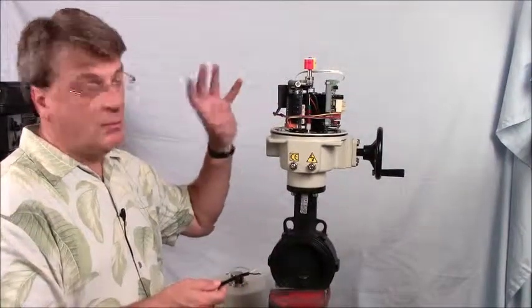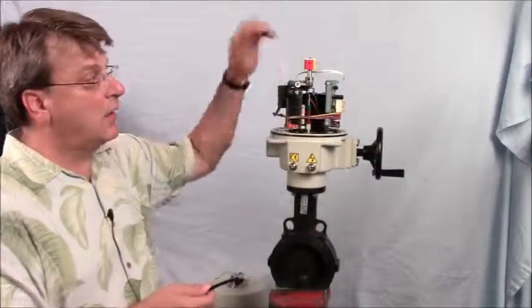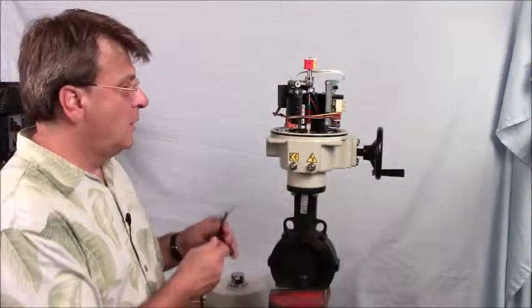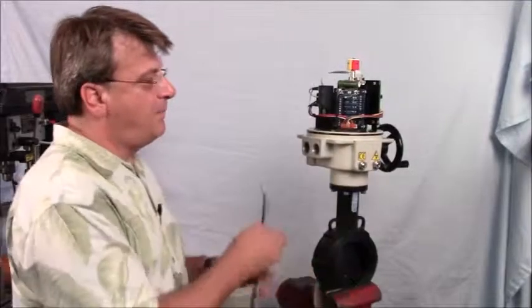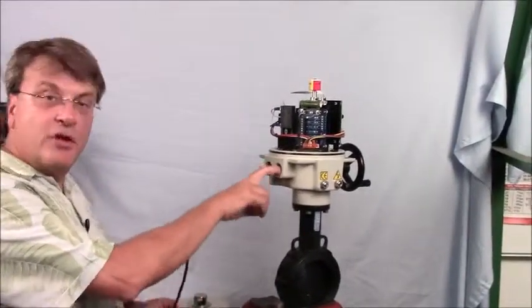First thing we'll do is hook up power to the switch card. Remember, power only goes to the switch card, not to the control card. Remember that power and control should be in separate conduits.